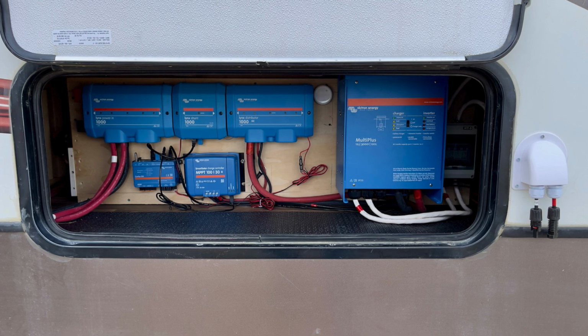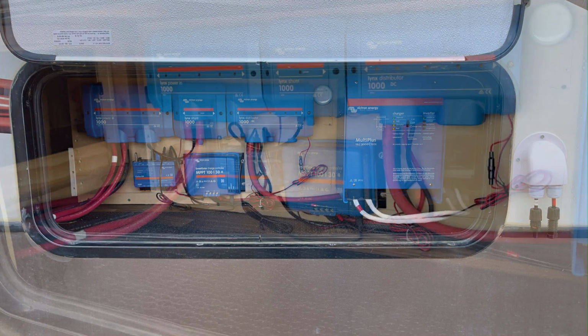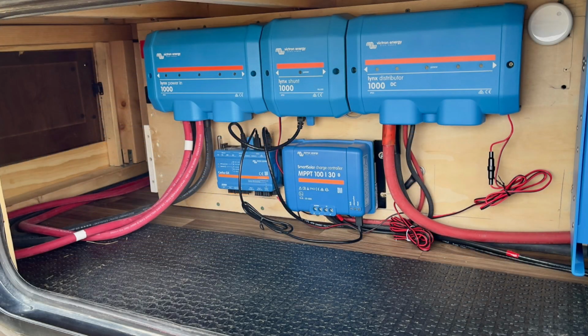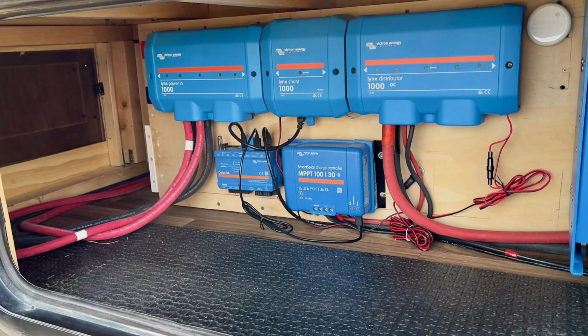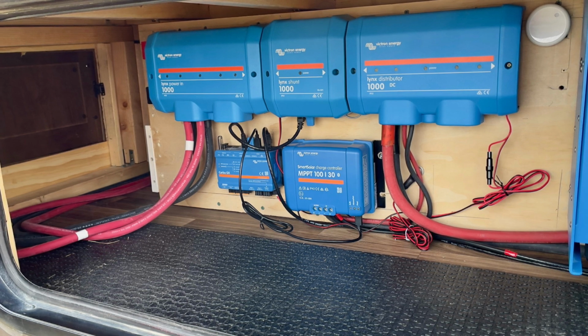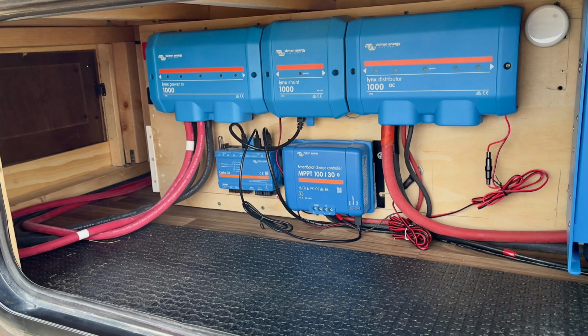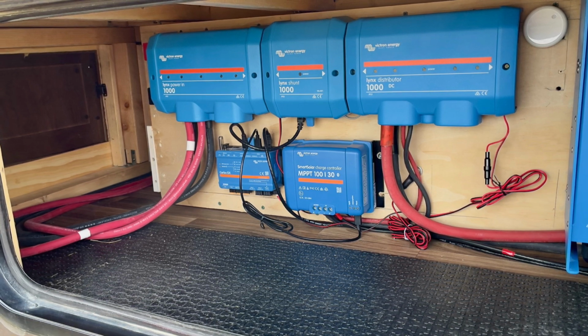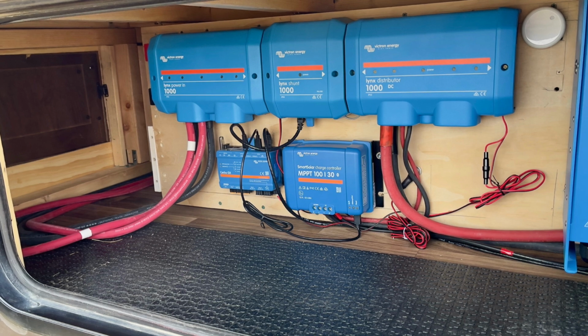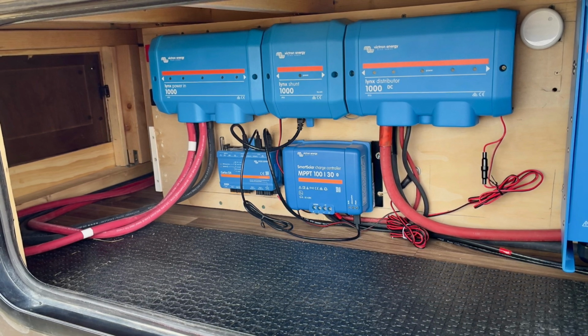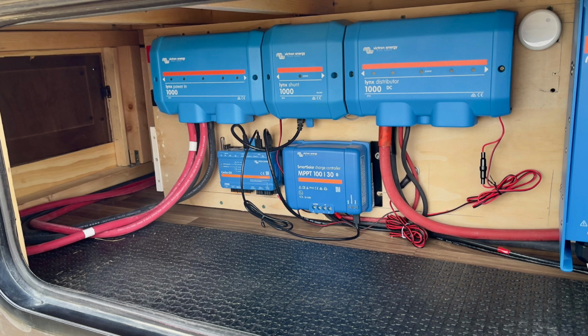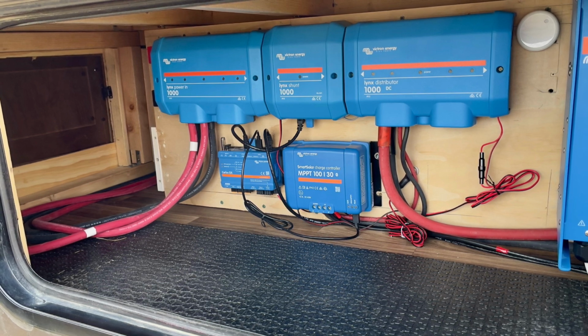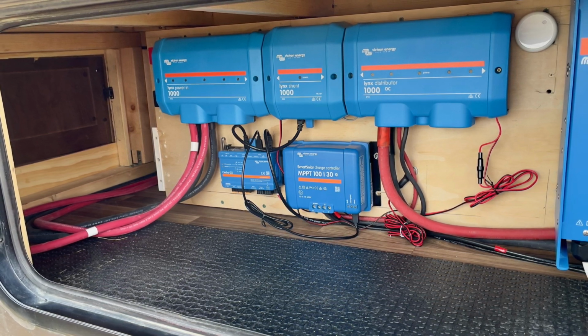This is why with our system, each battery has its own cable. We don't have to use 4-aught; it's sized according to the capacity of the battery. In our scenario, we're using 2-aught. The only time we use 4-aught is from our Victron inverter to our distributor. That's it - all the other batteries only use 2-aught wire.